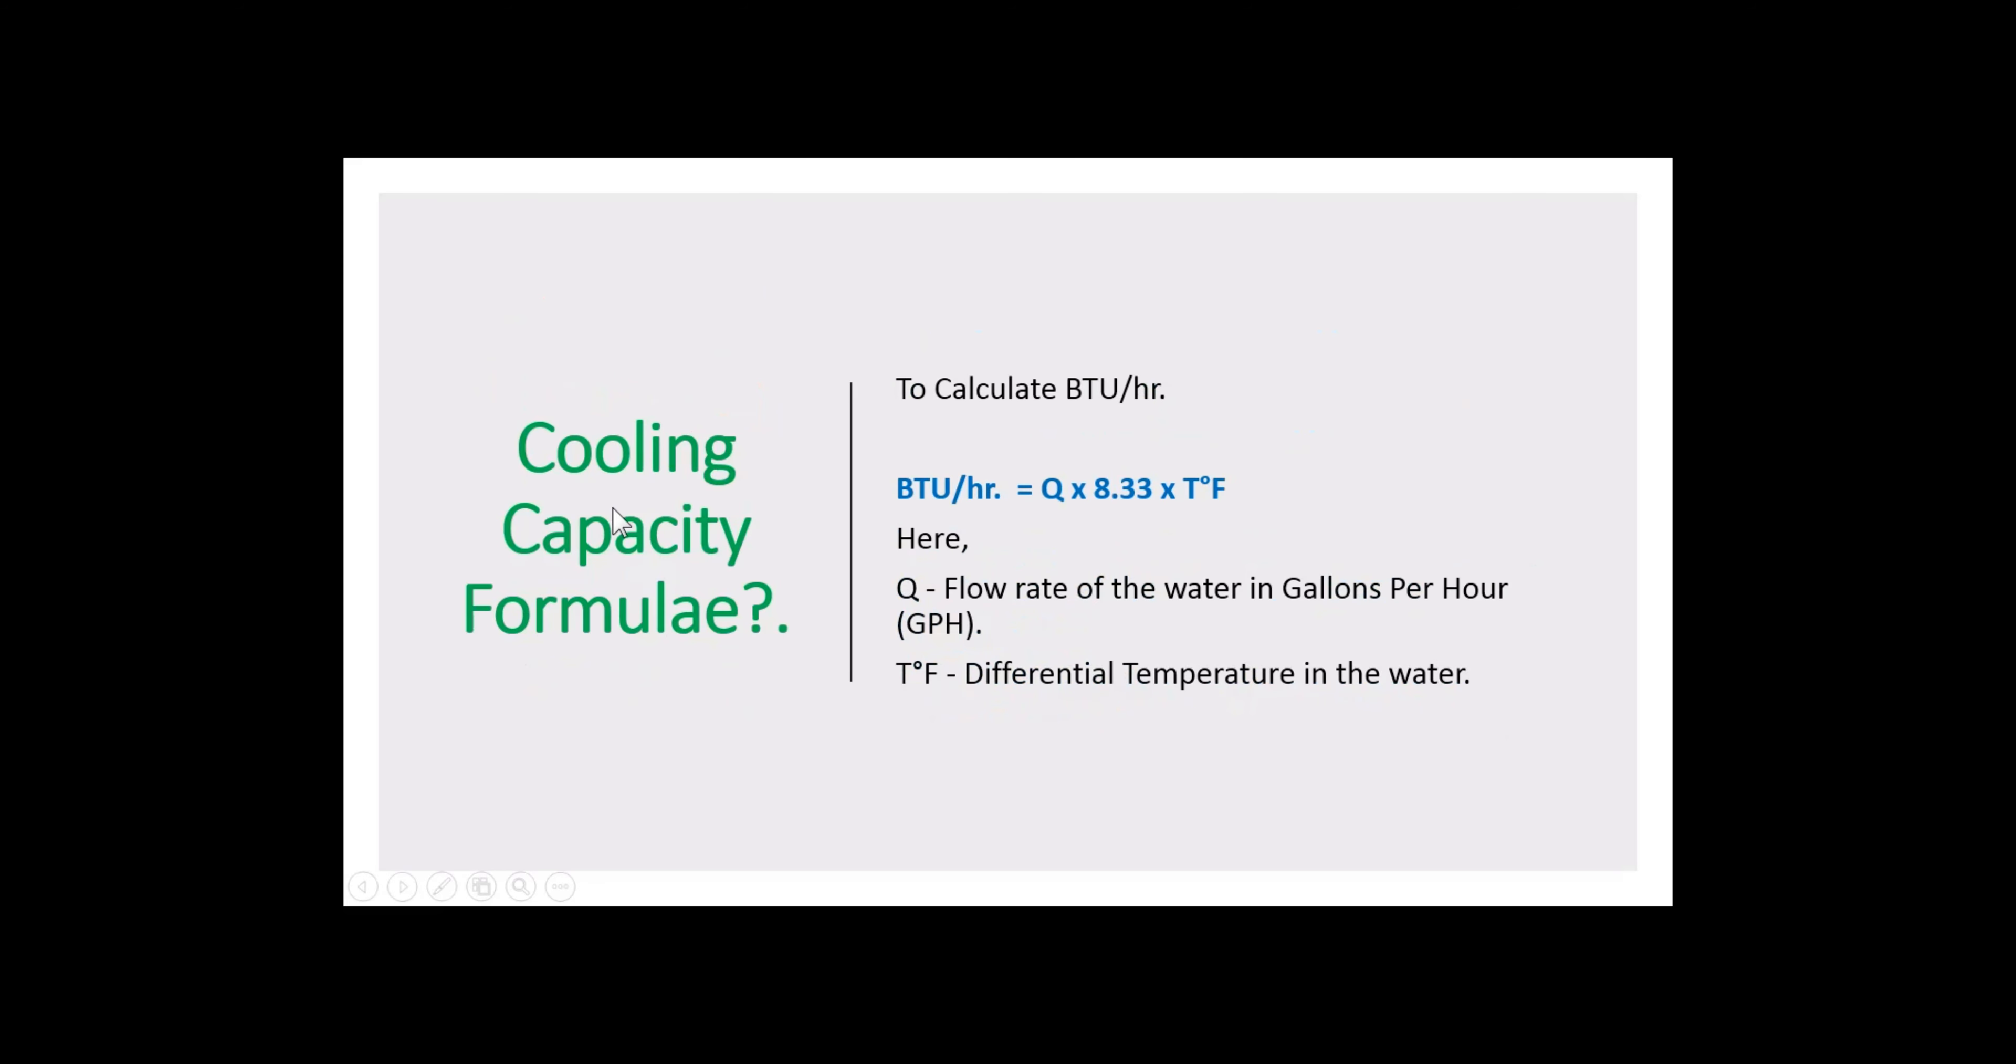Let us see what is the formula to calculate cooling capacity. To calculate British thermal units per hour, BTU per hour equals Q times 8.33 times temperature in Fahrenheit. Here, Q is the flow rate of water in gallons per hour.